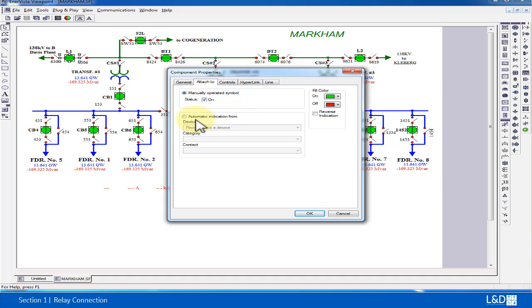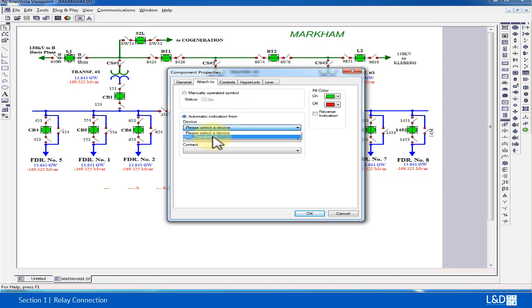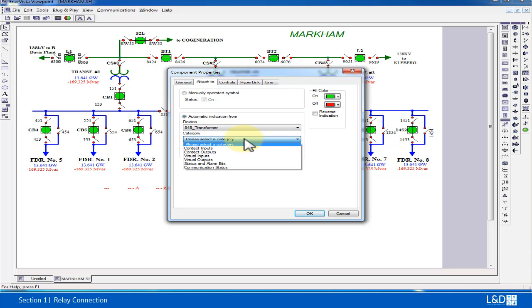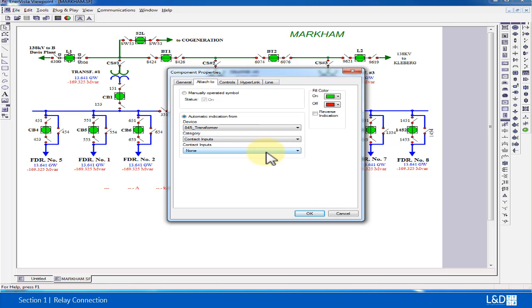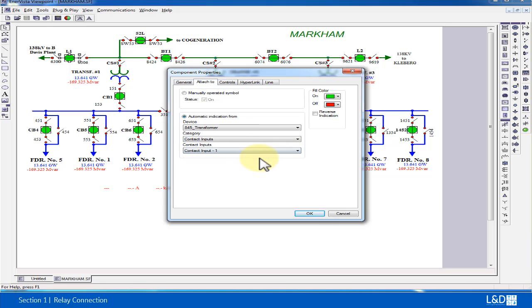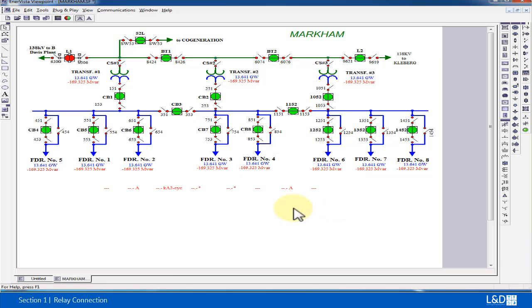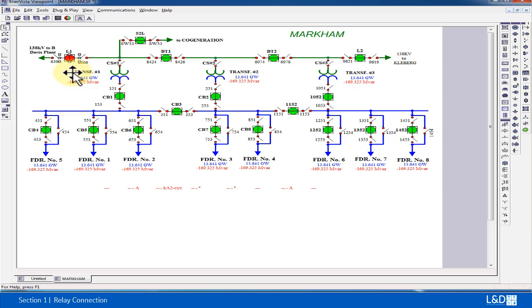By clicking this breaker open, I can associate this device by selecting the device number, 845 transformer contact input 1. This is associated with the breaker status, so now the status of the relay will be reflected in this single line diagram.